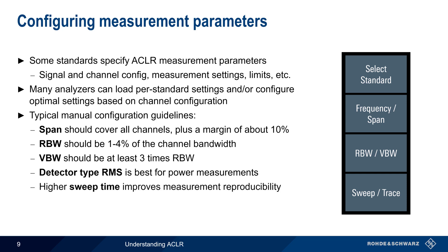Increasing sweep time tends to improve measurement reproducibility, although this will also increase measurement time. And finally, if the analyzer supports noise cancellation, this should be enabled as well.